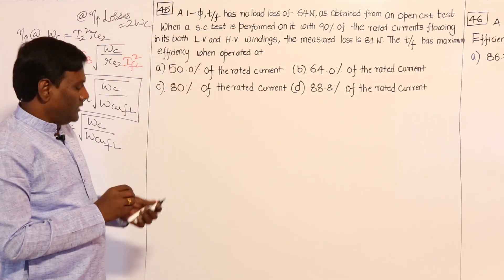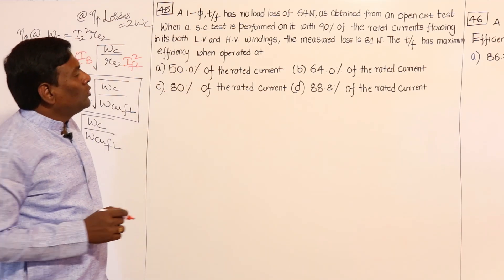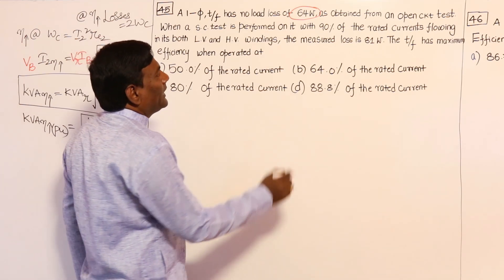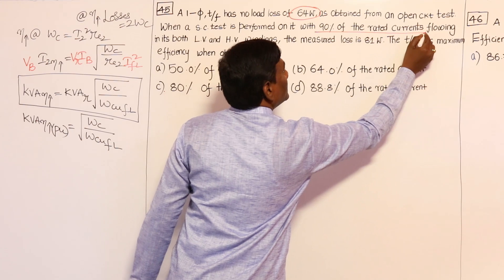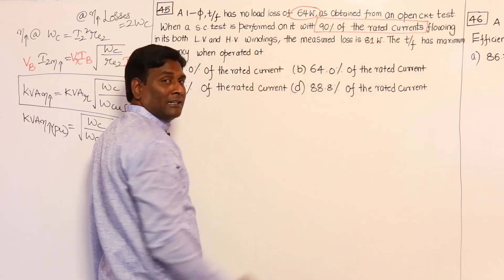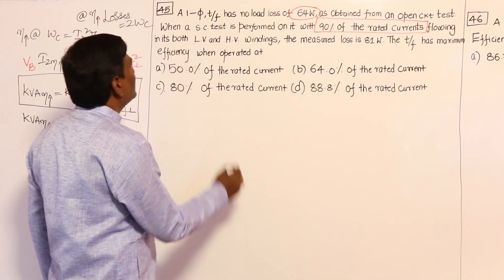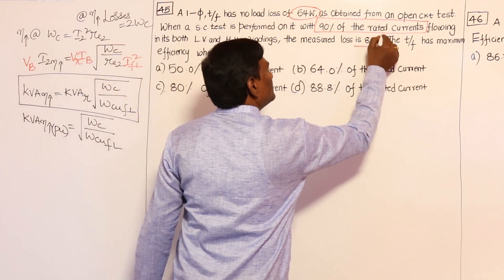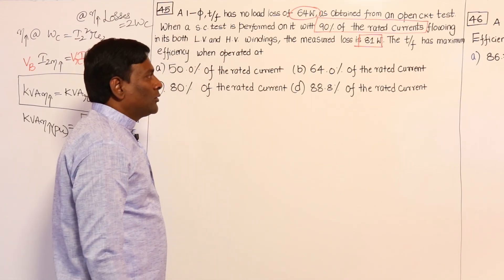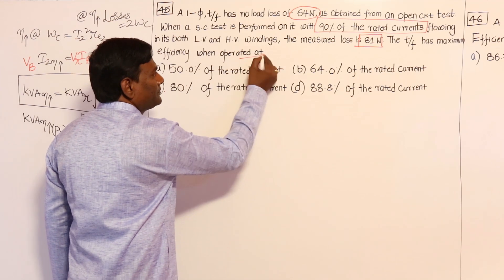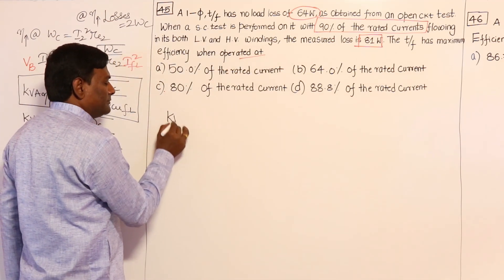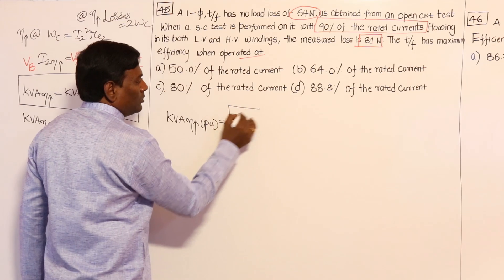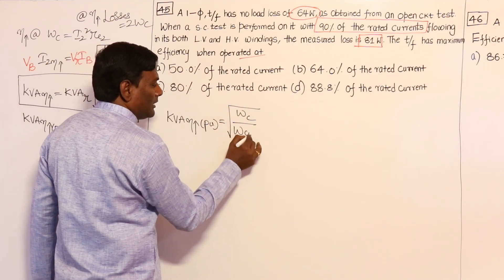Let us solve some problems. In this problem, a single-phase transformer has a no-load loss (core loss) of 64 W as obtained from the open circuit test. When the SC test is performed at 90% of rated current flowing in both LV and HV windings, the measured loss is 81 W — so copper loss is 81 W at 90% rated current. Find the KVA at which maximum efficiency occurs, in per unit.